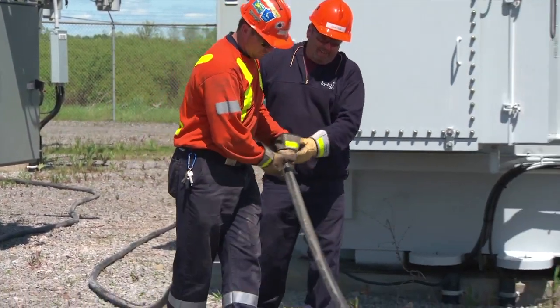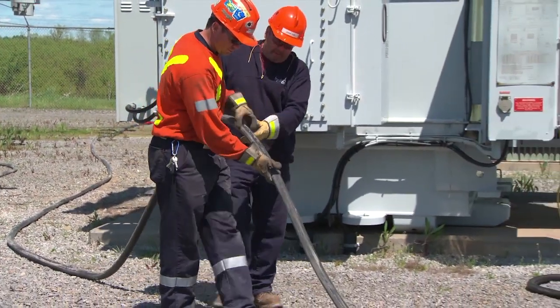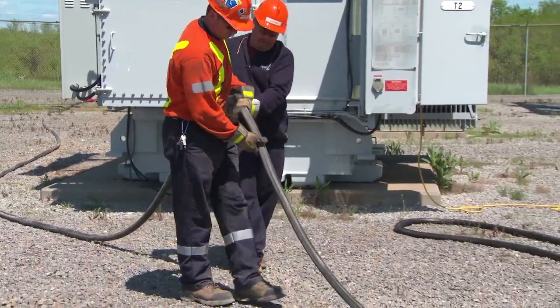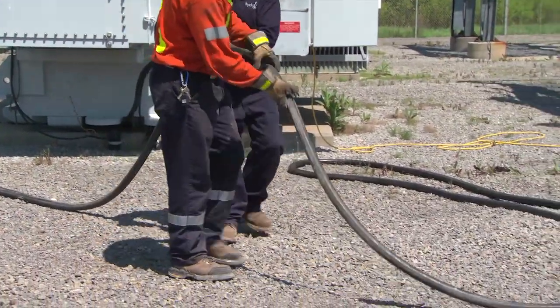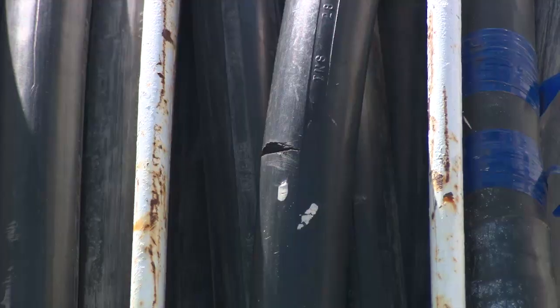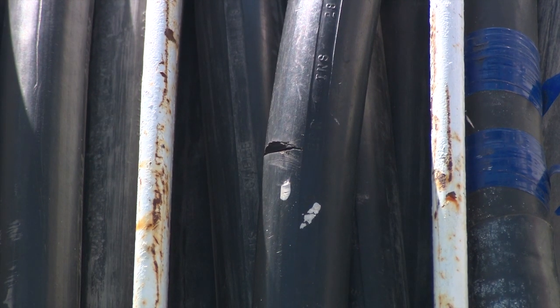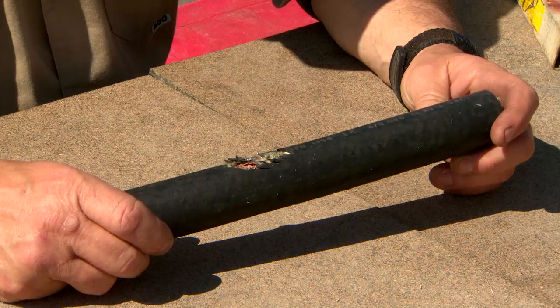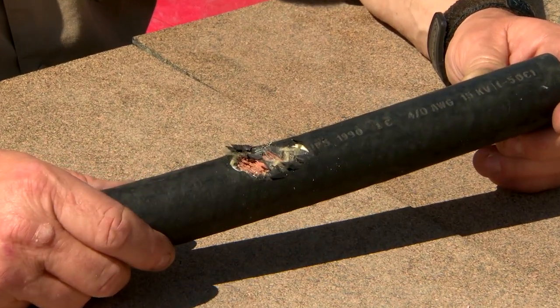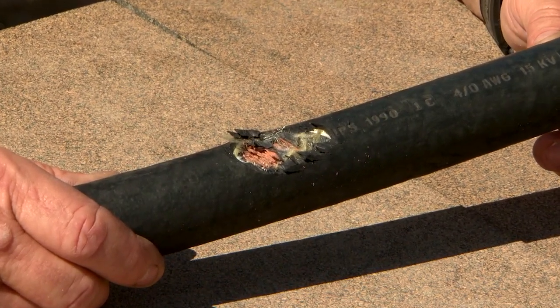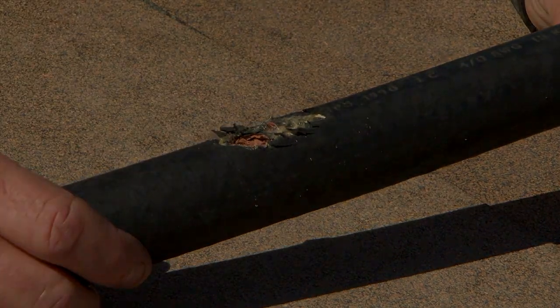The complete length of the cable must also be inspected for signs of mechanical damage, splitting, or blistering. If any heat blisters, tracking, or severe cracks are found, contact a cable expert, such as lines or station's cable crew. If significant repairs are done, the repaired cable should be high pot tested.